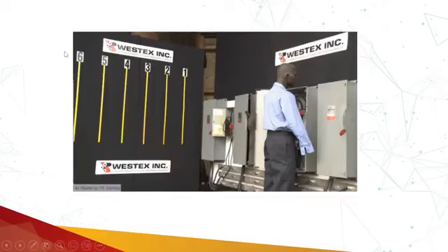Category 2 was used before. Now in the new standard, it is based on the amount of incident energy, whether the incident energy at that particular location is 4 cals per centimeter square, 8 cals per centimeter square, 25 cals per centimeter square, or 40 cals per centimeter square. So these types of terminologies will be used.